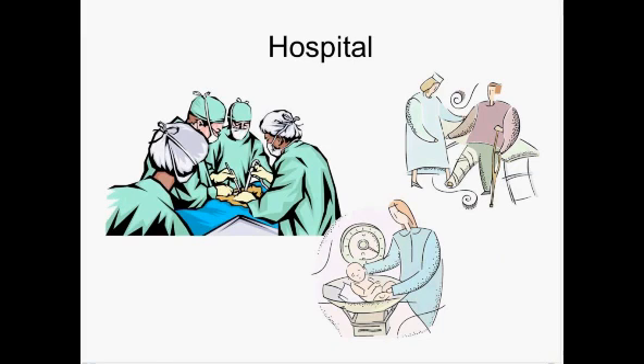In this application, everyone can understand the need for emergency power. We don't want to be on the operating table when the utility power fails. An important point to remember about a hospital or similar critical application is that in these cases, the emergency bus is divided into 3 separate loads.